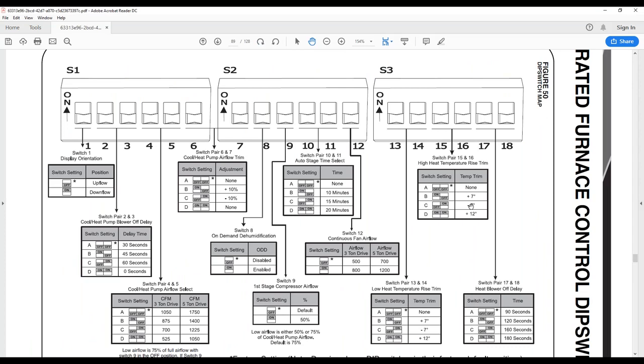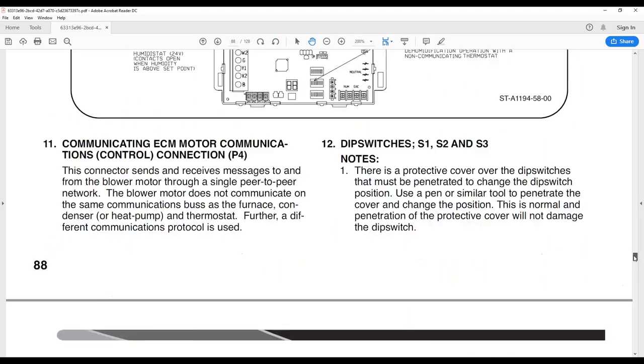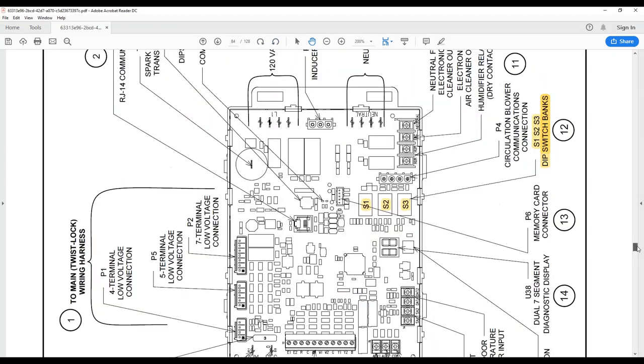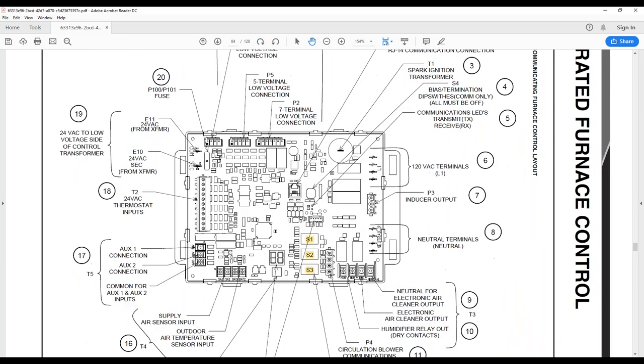So here are your dip switches on your gas furnace. I'm going to go back up a couple pages and show you where these are found on the control board. You're going to find S1, S2, and S3. These are switch bank 1, switch bank 2, and switch bank 3. There's a total of 18 dip switches right there, so there's 6 on each bank. S1 has 1 through 6, S2 has 7 through 12, and then S3 has the rest. So there's 6 on each one.